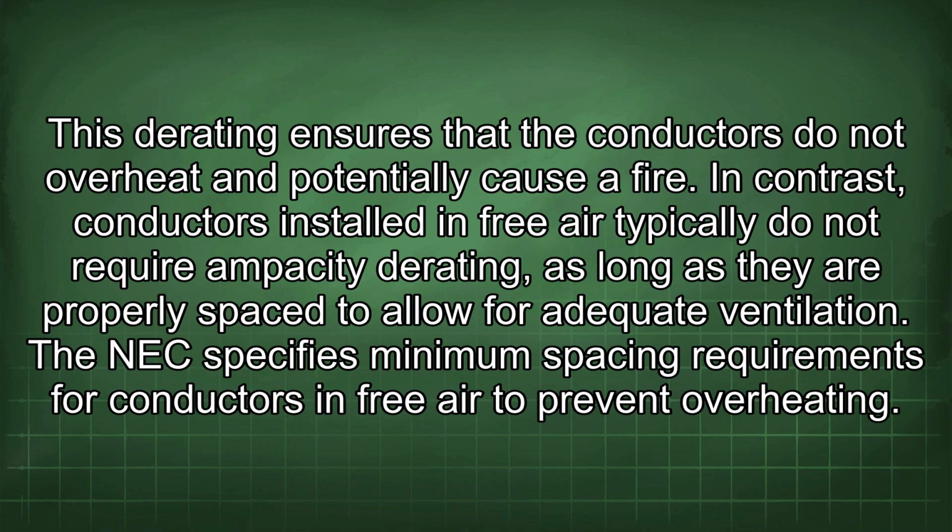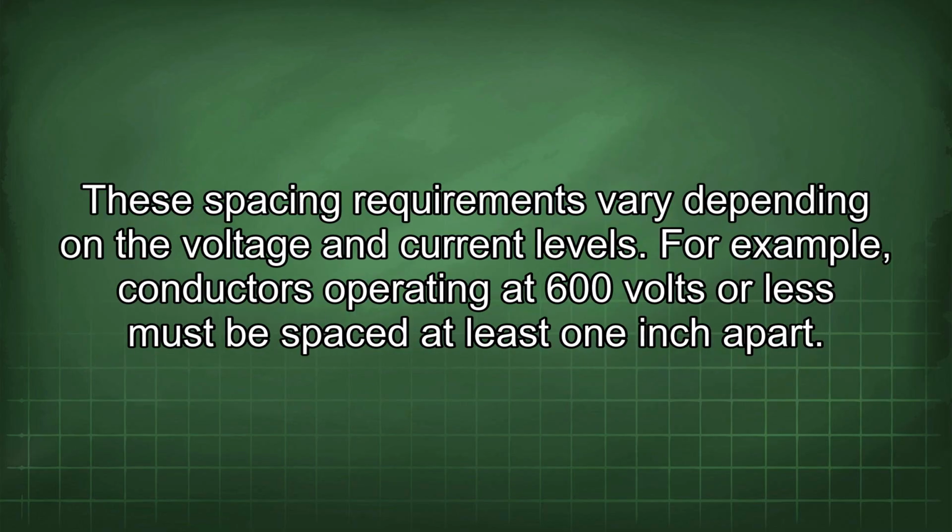In contrast, conductors installed in free air typically do not require ampacity adjustment as long as they are properly spaced to allow for adequate ventilation. The NEC specifies minimum spacing requirements for conductors in free air to prevent overheating. These spacing requirements vary depending on the voltage and current levels. For example, conductors operating at 600 volts or less must be spaced at least 1 inch apart.